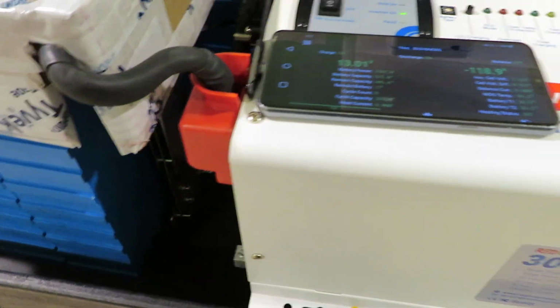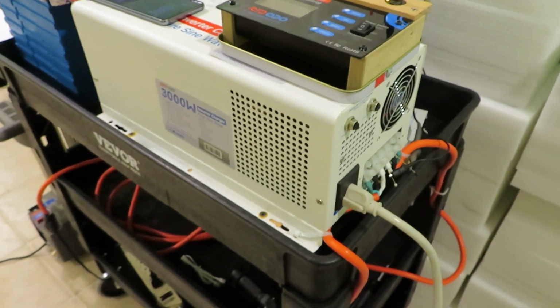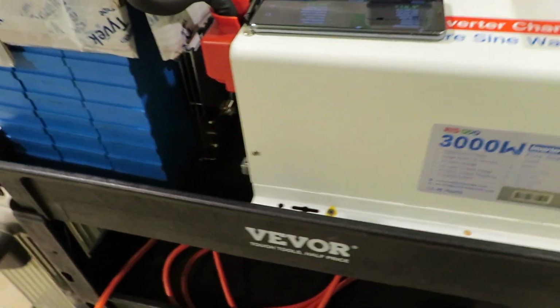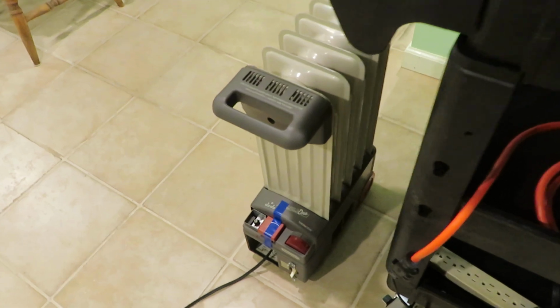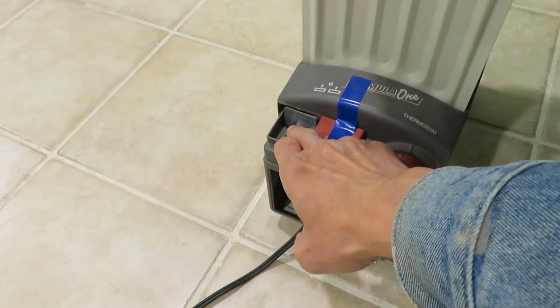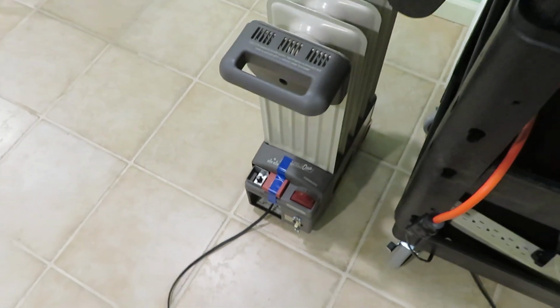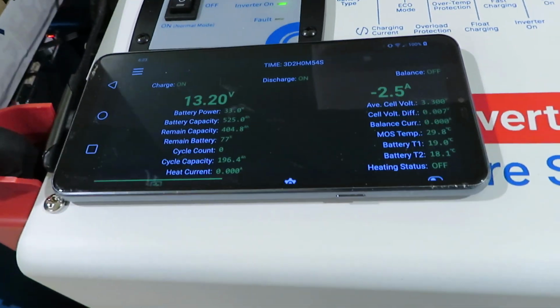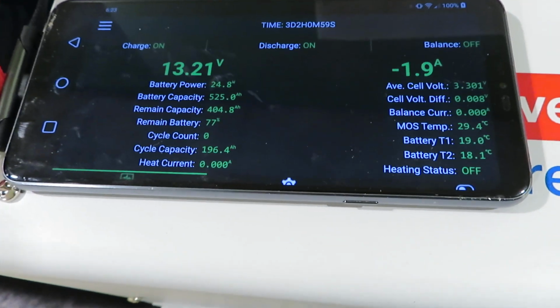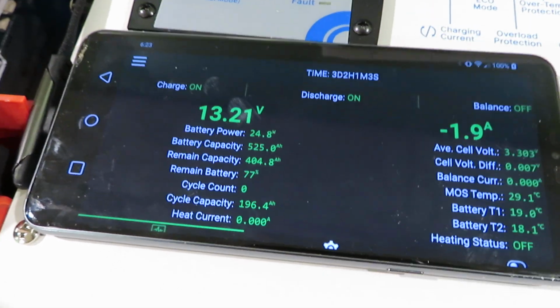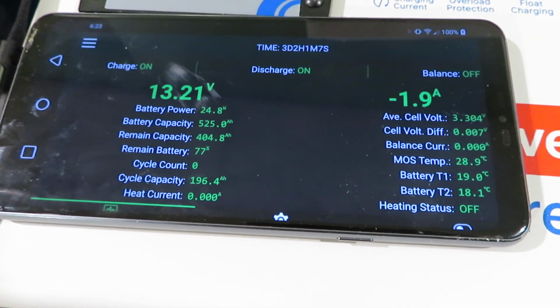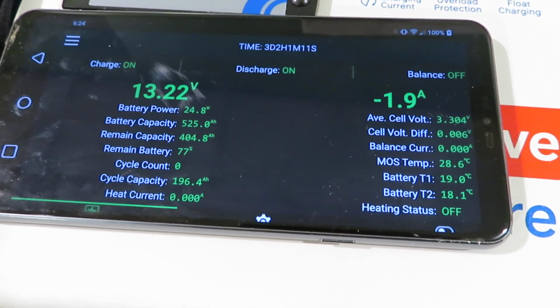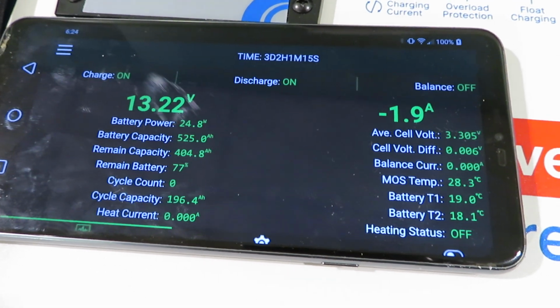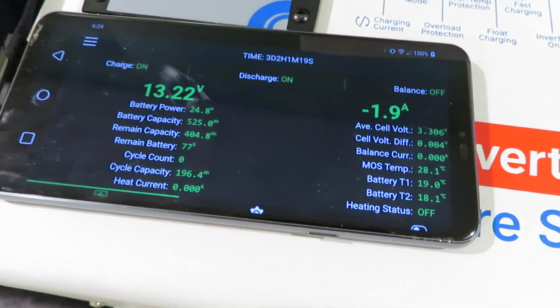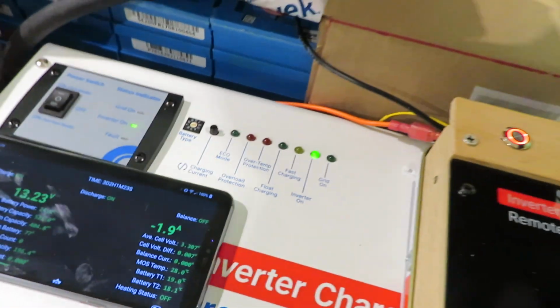So this is basically the test I wanted to do. Let me shut off the electricity, or at least shut off the heater first. I just shut off the heater, and now the fan goes off. It appears that when the fan was on, it drew about 2.5 amp of parasitic overhead; now without the fan it's drawing about 1.9 amp for the system. So the fan is off.